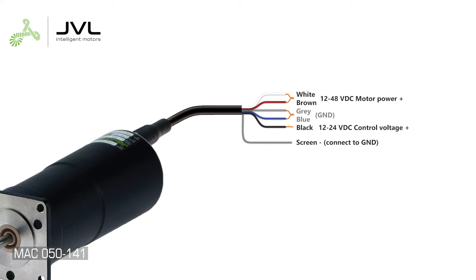The wires also share the same color coding. Connect both brown and white to the motor power plus. Connect both blue and gray to ground. Connect the black wire to 24 volt DC control voltage.